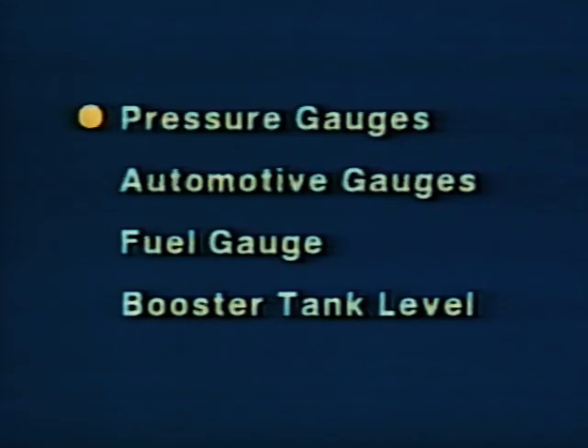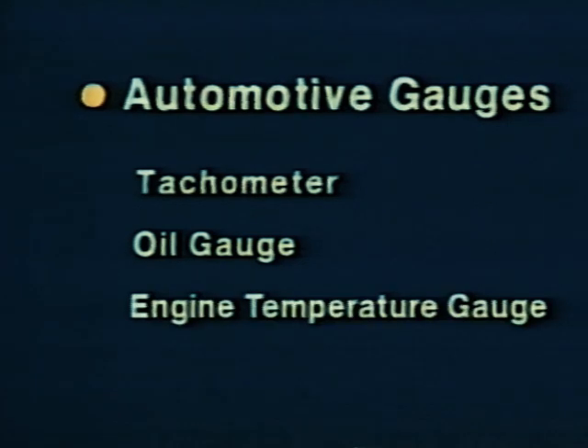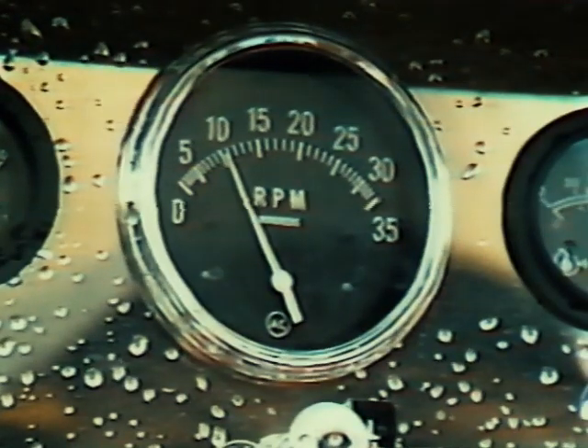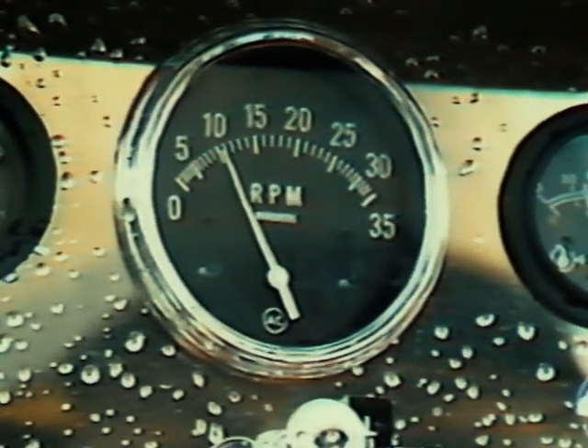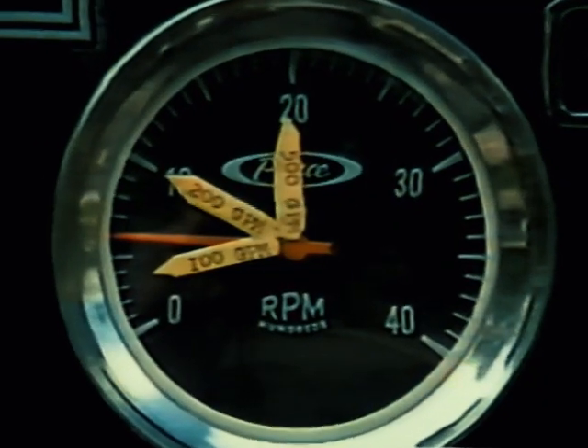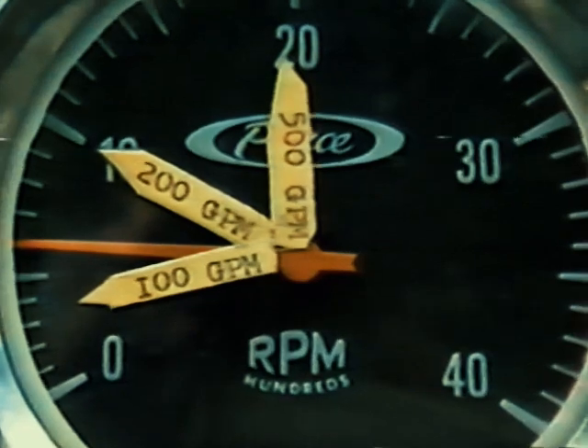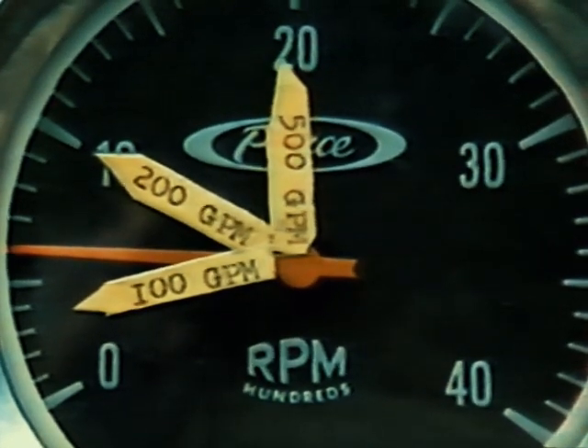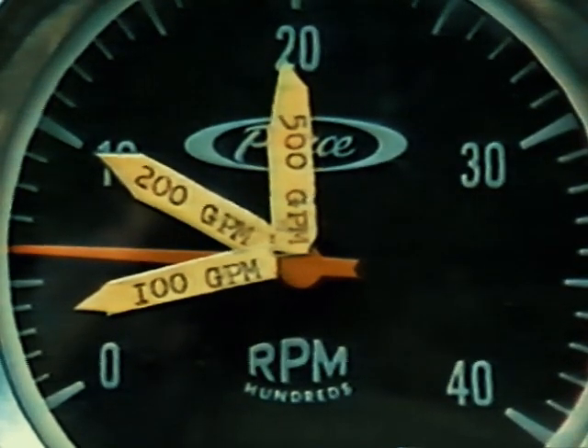To protect the engine and make sure it is operating at peak performance during the pumping operation, there is a set of automotive gauges mounted at the pumping station. These gauges usually include a tachometer, oil gauge, and engine temperature gauge. The tachometer indicates the speed of the engine crankshaft in revolutions per minute. A tachometer may also have calibration marks to indicate engine speeds required for corresponding pump capacities.